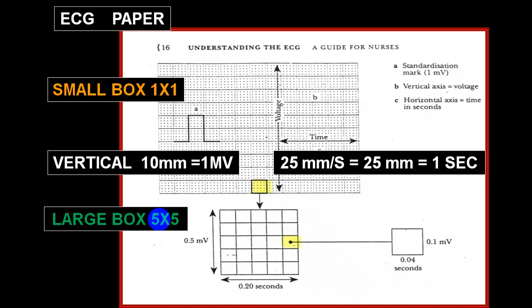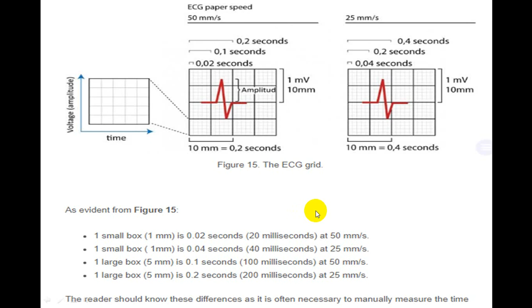And if you have a record with a 50 millimeter speed, one small box will be 0.02 second. You have to keep this in mind, because when the measurement is at 50 millimeter speed, the paper will move out fast. So 50 millimeters will come out in 1 second. You have to keep that in mind.